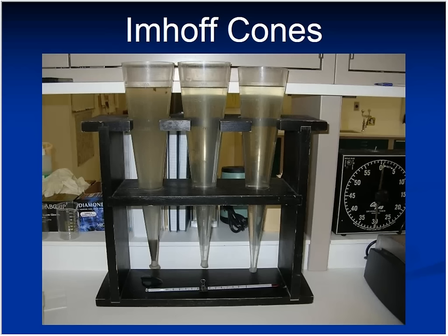You see in this picture are Imhoff cones. That's how we test for settleable solids. Basically a 1 hour test. You put a 1 liter sample into the cone, let it sit for 45 minutes. At that point, you take a stirring bar and just gently rub the wall to make sure nothing's clinging. You give it another 15 minutes and it's a direct read.